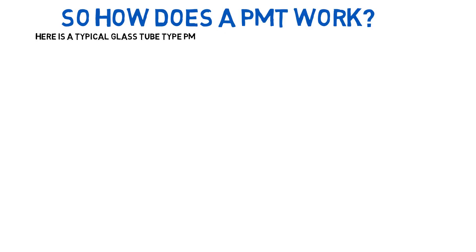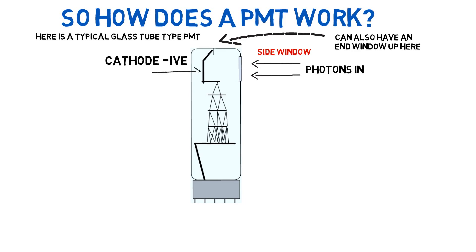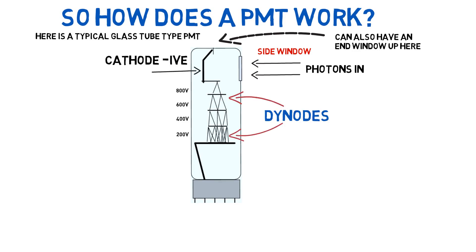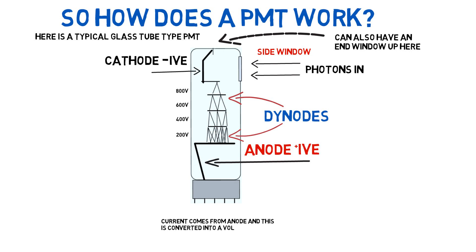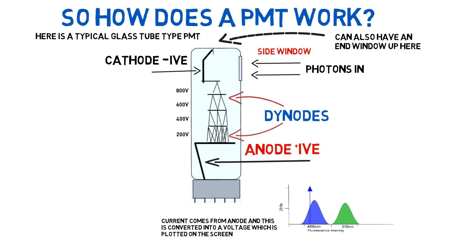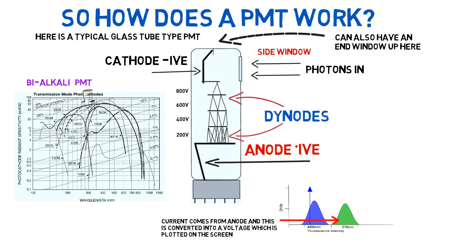Here's a typical glass-type PMT with a side window where the photons come in. They hit the cathode, and then you see the dynodes going down to the anode, which is positive. It is the dynodes where the high voltage is applied. The current from the anode is converted into a voltage, which is plotted as histograms. The frequency range differs for the bialkali and multialkali PMT, with multialkali being slightly higher. The spectral response depends upon the materials the cathode is made from.